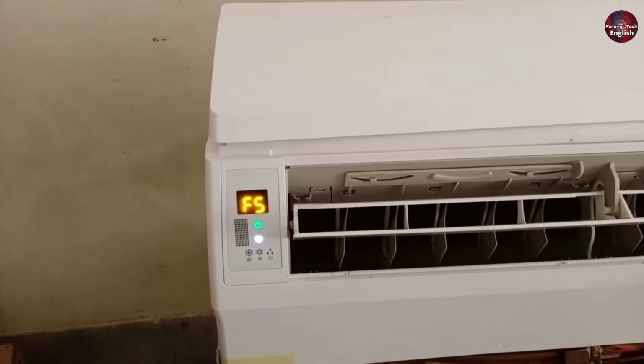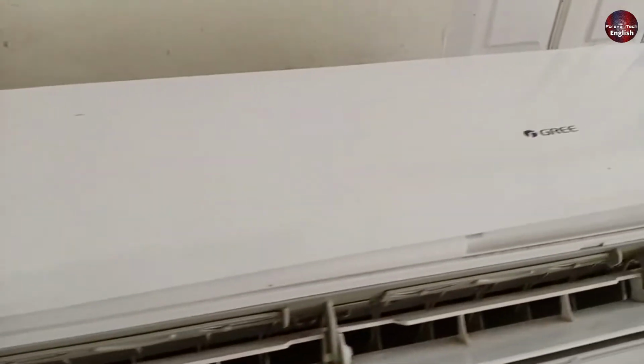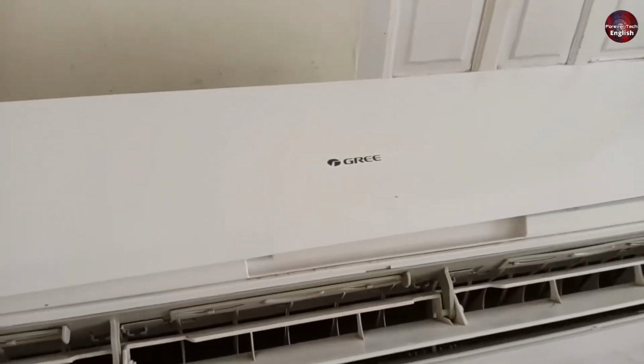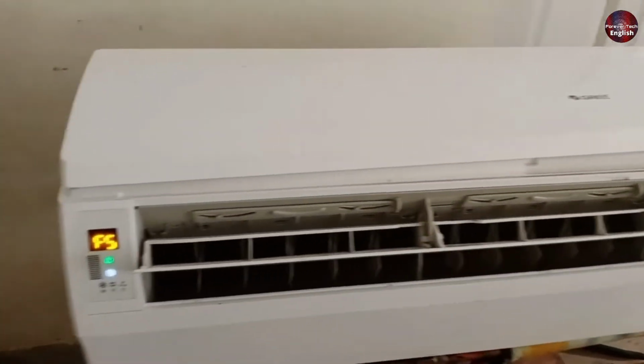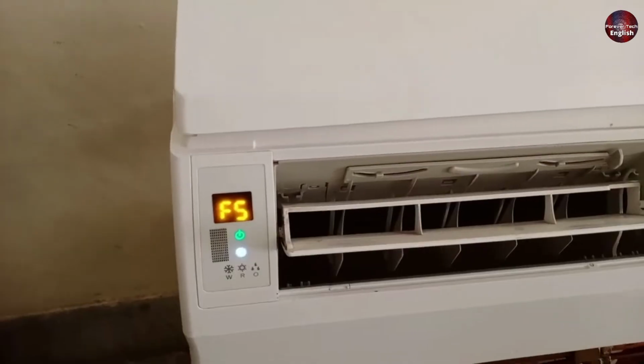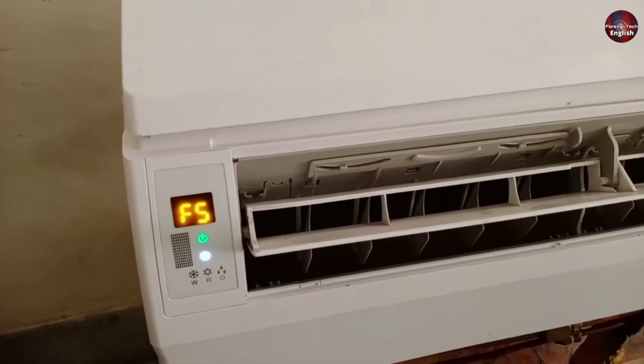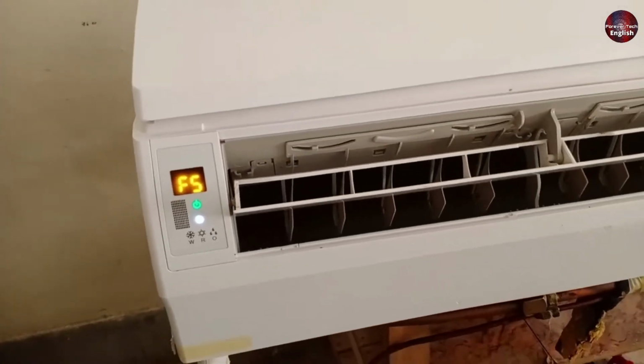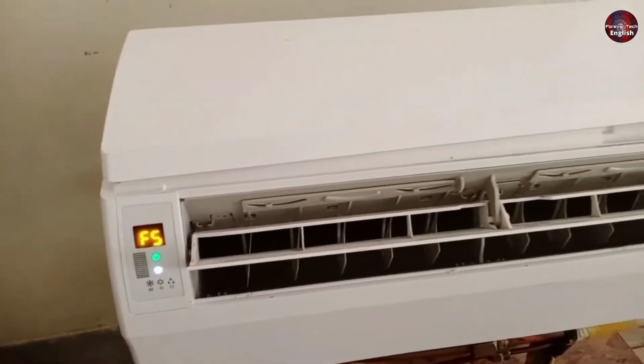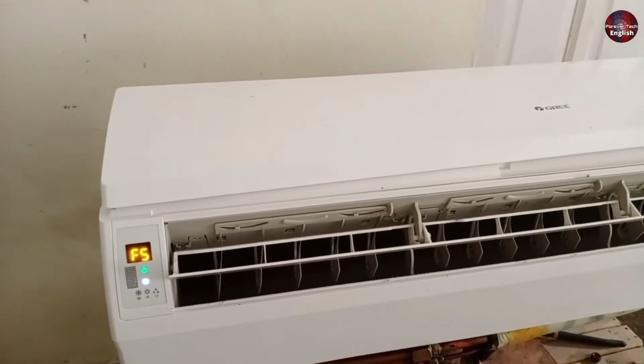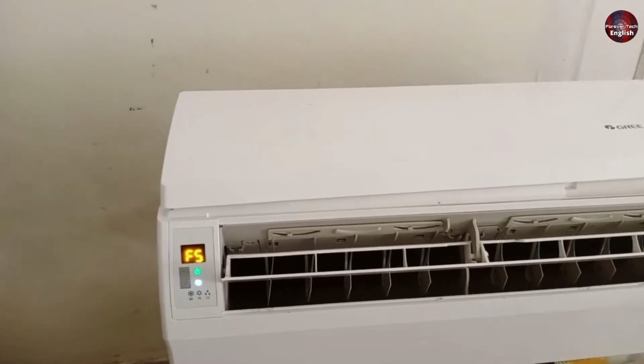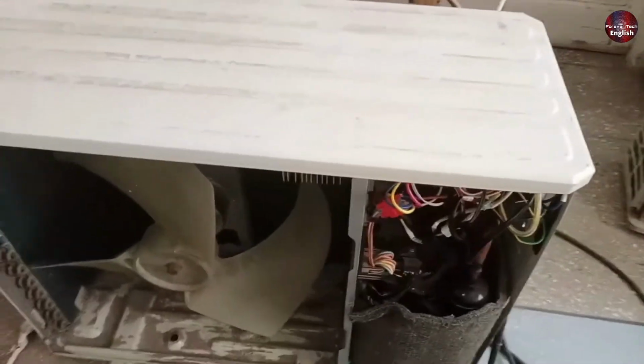Now, let's talk about the next error, F5. We will explain in complete detail why the F5 error code appears on the display of a GREE DC inverter air conditioner, what the causes are, and how you can fix it. Let's head over to the outdoor unit, because this is also an outdoor-related fault. We'll show you what causes this error and which component might be faulty that triggers the F5 error code. Now we are at the outdoor unit.